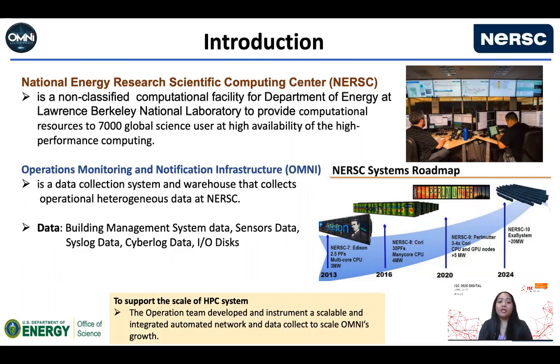OMNI stands for Operations Monitoring and Notification Infrastructure. It's a data collection system and warehouse that collects operational heterogeneous data at NERSC, including building management system data, sensor data, syslog data, cyberlog, and I/O disks. With the delivery of the new HPC system and because of the scale of the new machine, the data rate available is expected to be 100 to 1,000 times faster. Thus, exascale size of data are anticipated to be sent to OMNI.